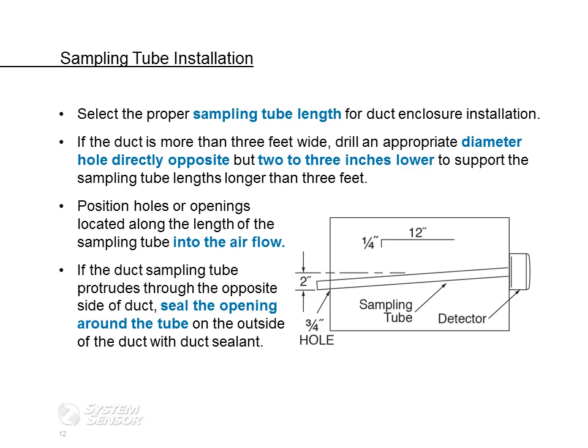Now, it can be supported one of two ways. It can be supported either by drilling the hole on the far side of the ductwork and using that. You may run into instances, though, where you can't make that penetration on the far side of the ductwork due to lack of space or the length of the sampling tube that you're using. It's also permissible to put a wire hanger in the middle of the ductwork to support that sampling tube. The thing to remember is that sampling tubes greater than 3 feet have to be supported one of those two ways.